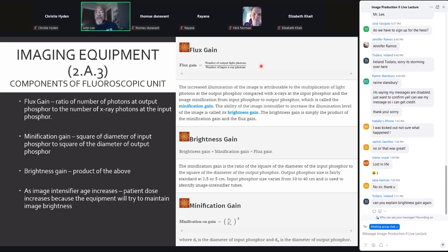The minification gain is the ratio of the square of the diameter of the input phosphor to the square of the diameter of the output phosphor. The input phosphor is the big end close to the patient. The output phosphor is the small end where the light is going to come out. Therefore, the bigger number goes on top in this formula. Now, the input phosphor diameter is variable. You can have a tri-field or a dual field image intensifier, which means you can have 2 input phosphor sizes or 3 input phosphor sizes. So based on whichever one you're using, you'll plug that into D1 on that formula.